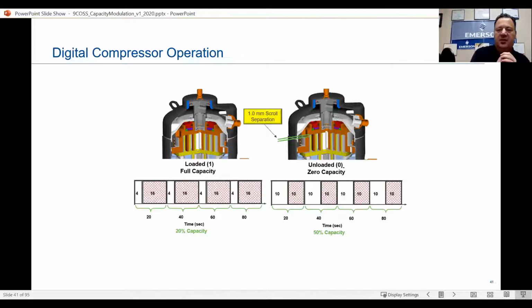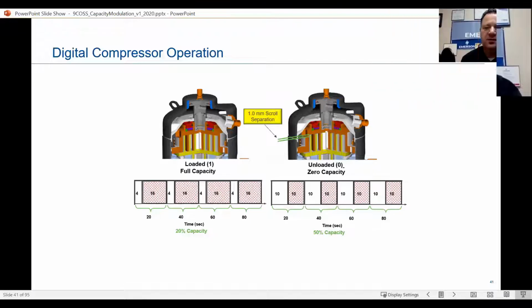Okay, and by the inertia of that gas flowing through there, it doesn't affect it at all. It keeps moving. It's a quick, like I said, 16 seconds back on, but from the inertia that we're already pushing from the original gas flow, it keeps flowing. It's just like speeding down the highway. When you put your brakes on, you don't come to a complete stop. You still roll and coast. It's the same concept, okay? So at 20% capacity with 20-second increments, we're on for 4, we're unloaded for 16, loaded for 4, unloaded for 16, and so on and so forth. At 50%, same concept. 10 seconds loaded, 10 seconds unloaded, 10 seconds loaded, 10 seconds unloaded. Okay, that 1 millimeter, just separating that scroll tips and stop pumping like that.